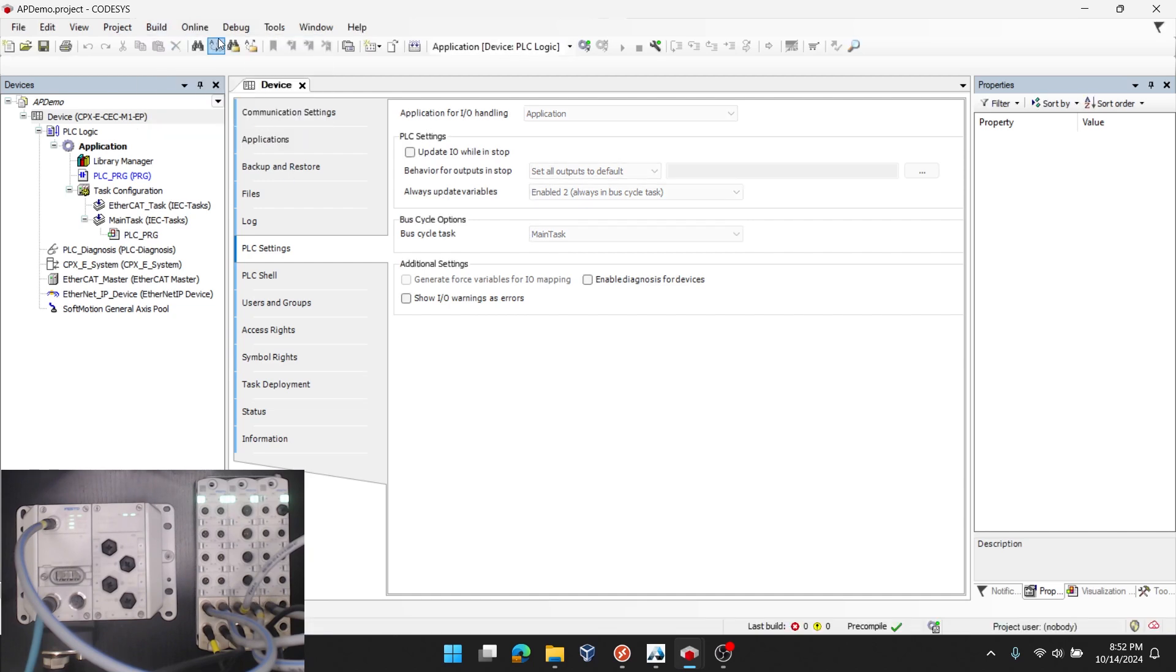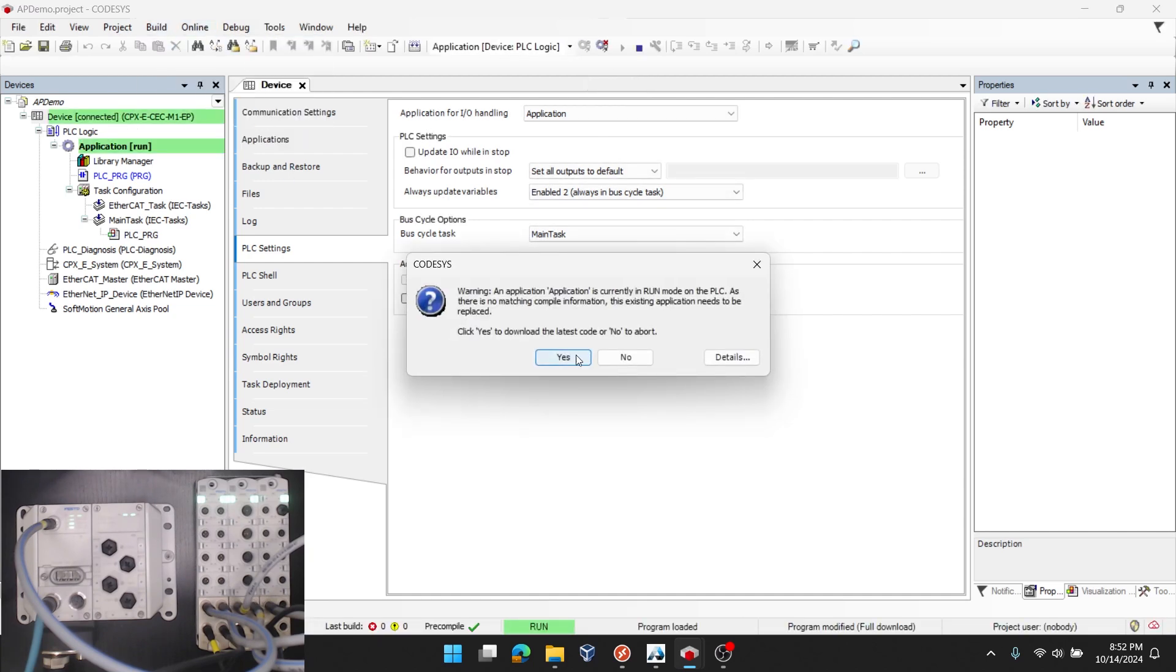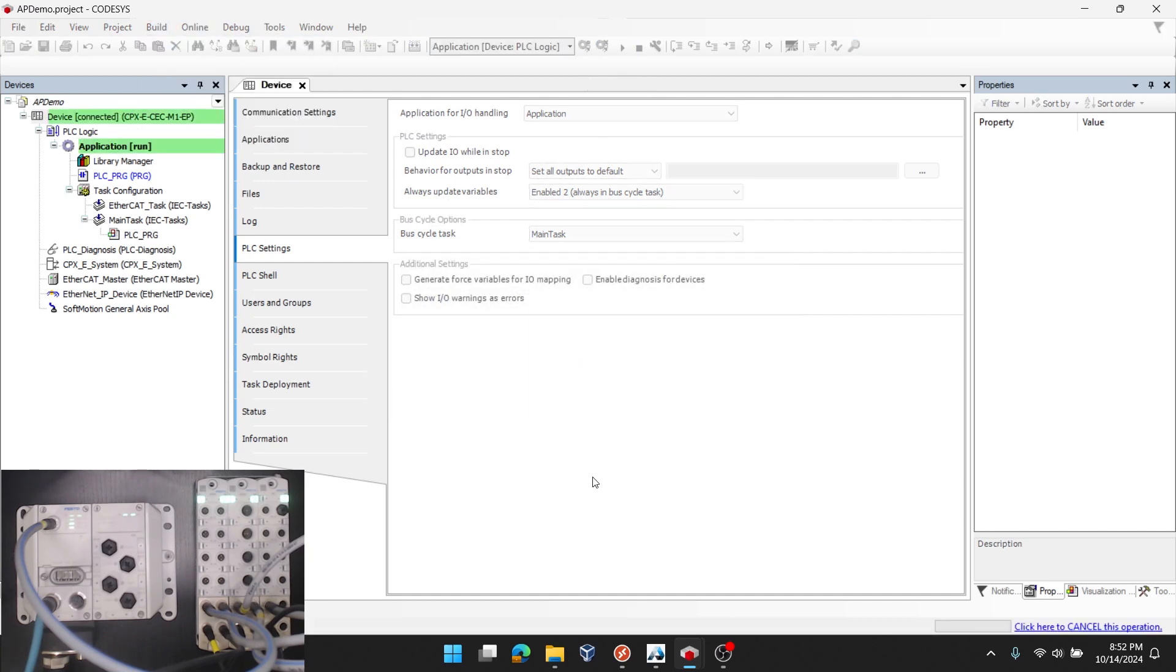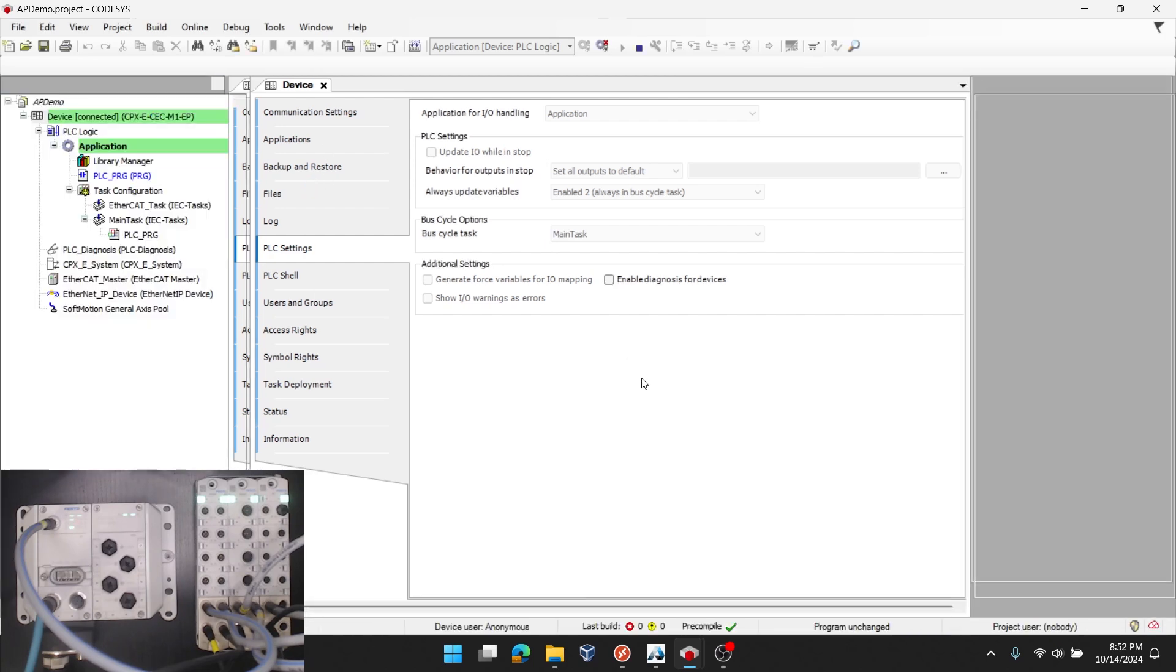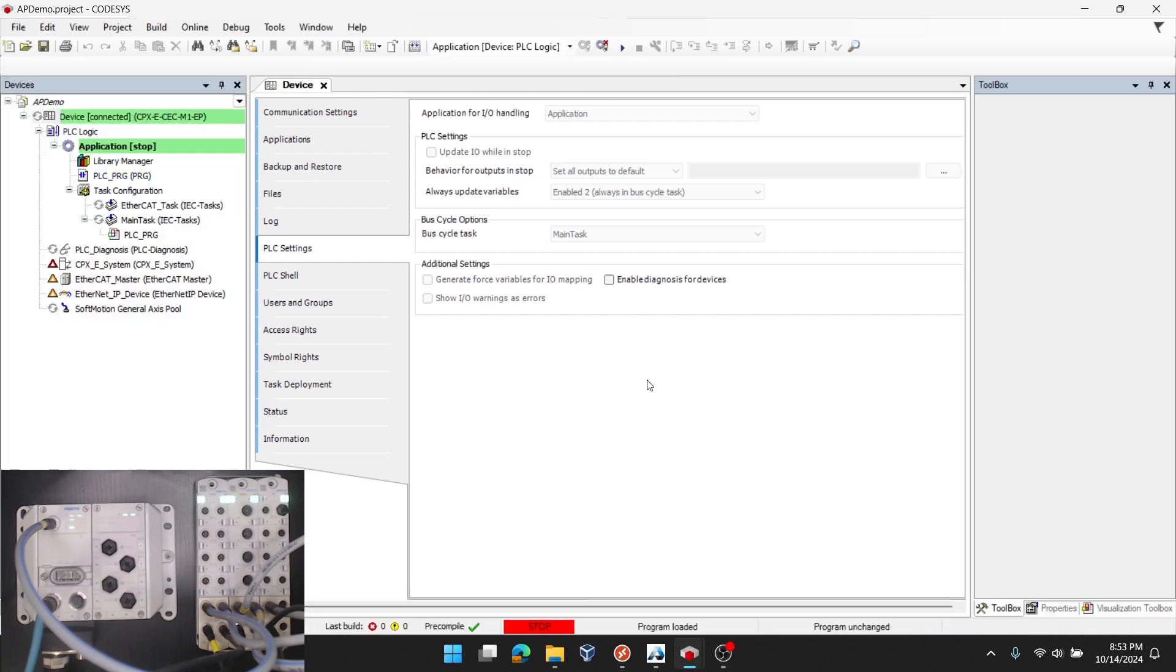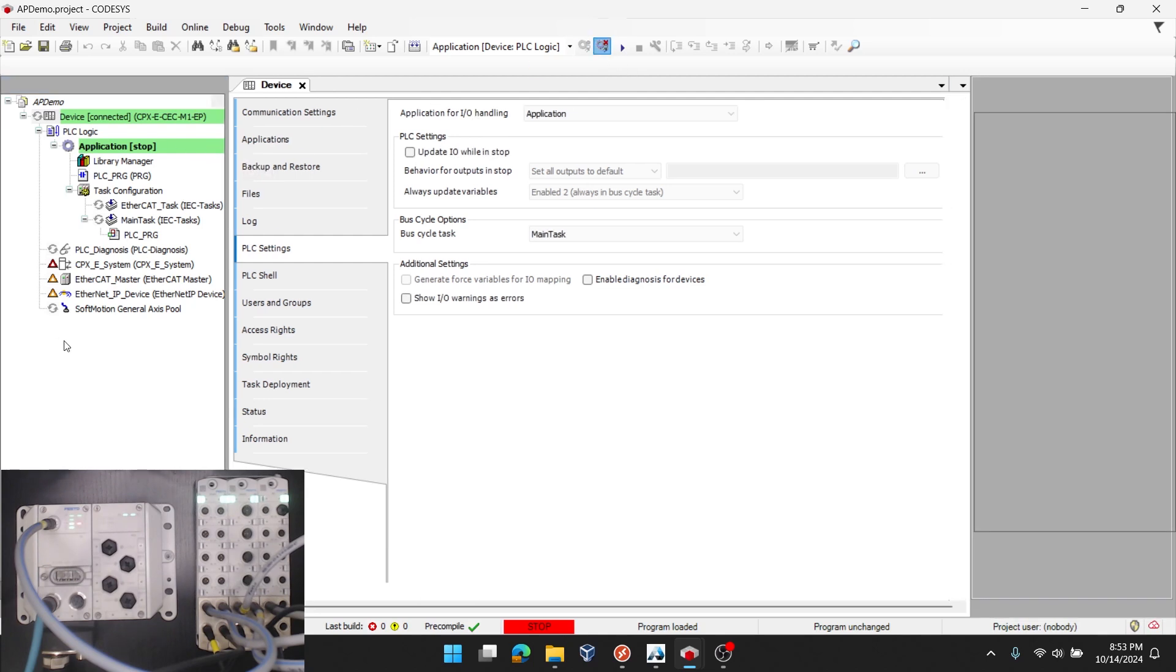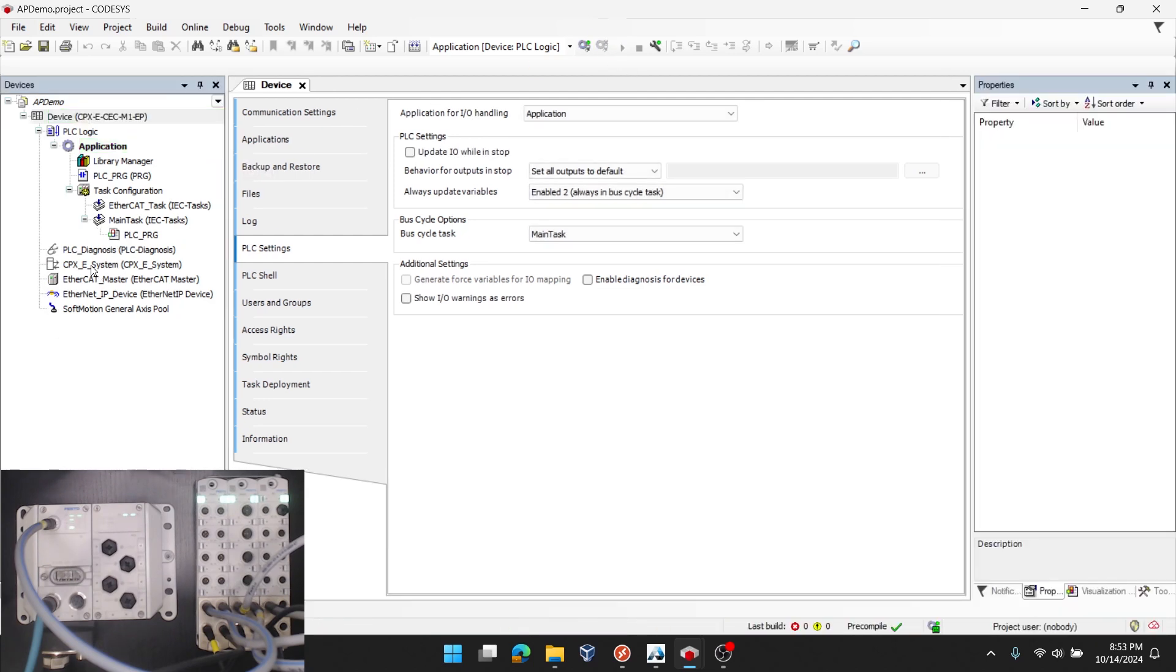Now if I want to connect to the PLC to verify that setting, I'll build and then log in. Acknowledging the pop ups here. In stop mode, I am able to connect to the PLC. So the next thing I'll do is go back offline and expand the CPXE system. This will first allow me to add the IP20 Rack IO.